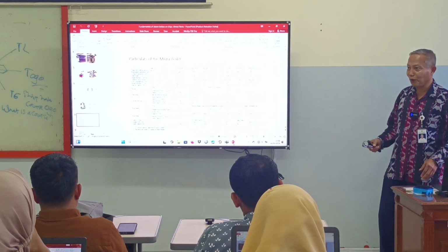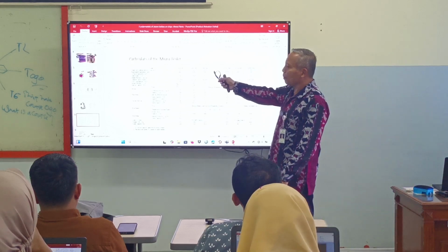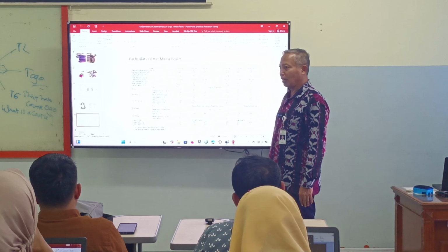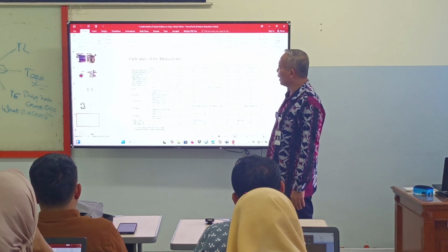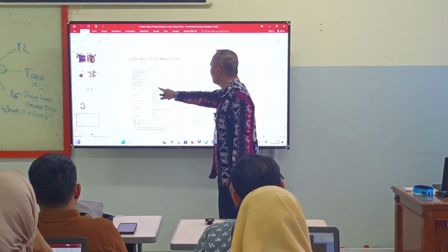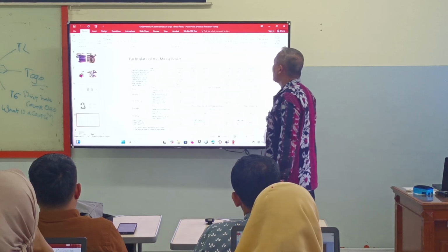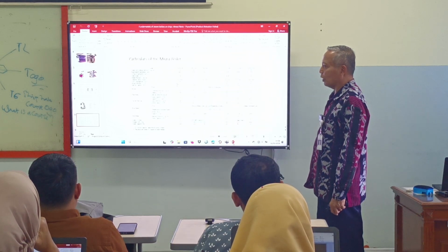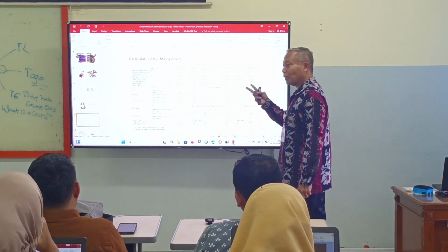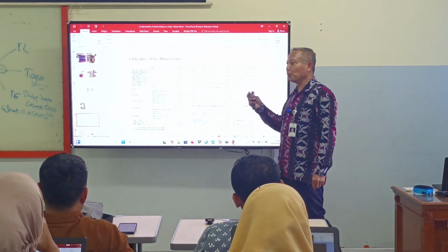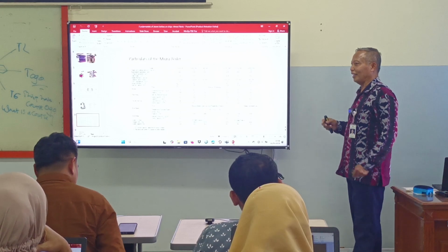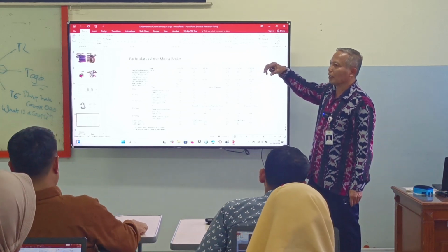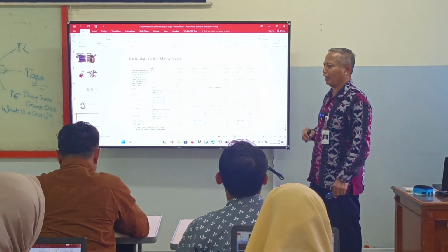Mr. Sapta, do you know the main auxiliary boiler in the engine room? How many bar is the steam pressure? 5 to 7 bar. At 5 burning starts and at 7 burning stops.